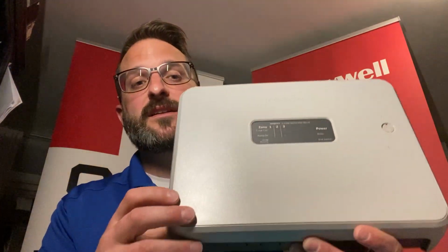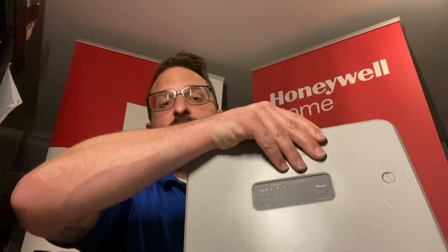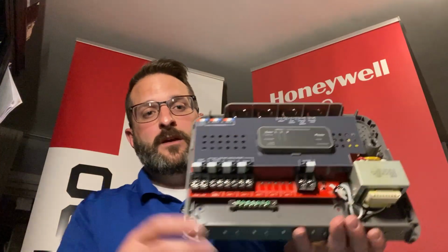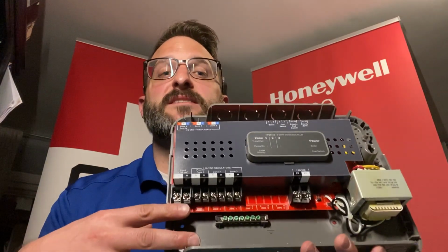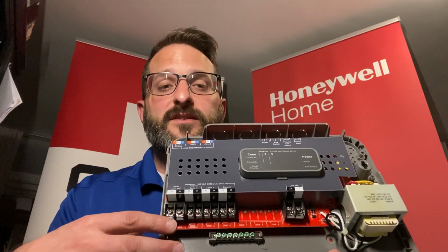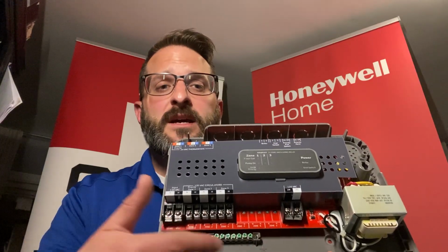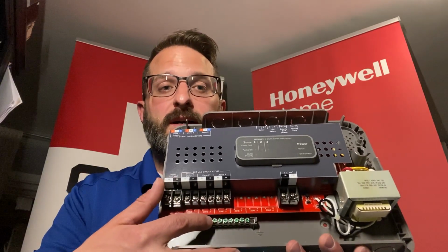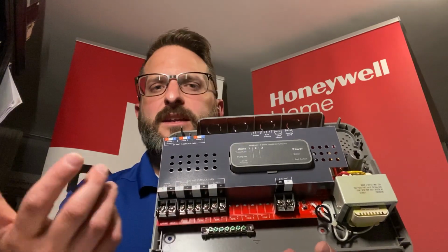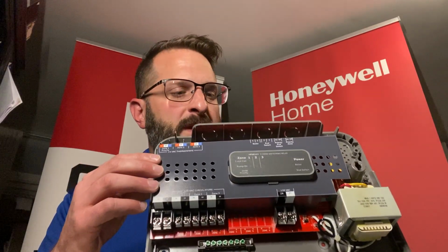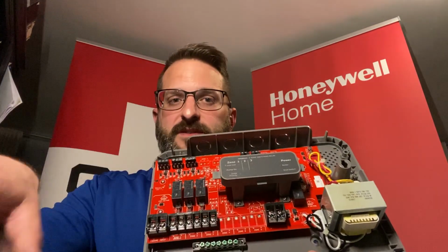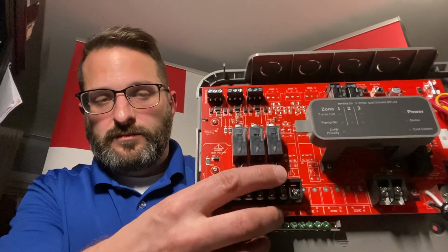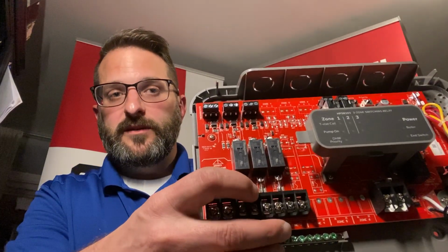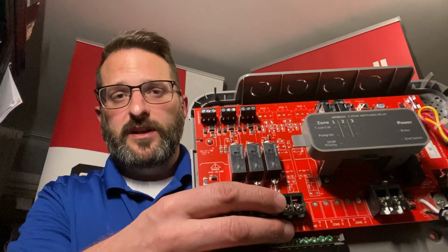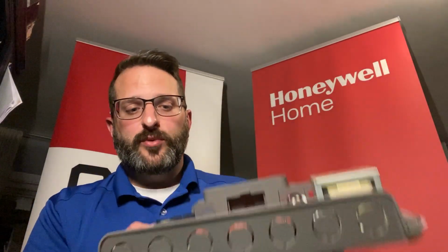So moving on to the switching relay, first thing you'll notice is that it's a little bit taller. That is because we added some extra space on the bottom, about 1 inch, to do our line voltage wiring for the pumps. And then we have a dedicated grounding bar for our line in and each pump that you have for the system. So actually we pop this off, and then each relay is independently fused, and then these are industrial strength relays. So it's a really quality product.